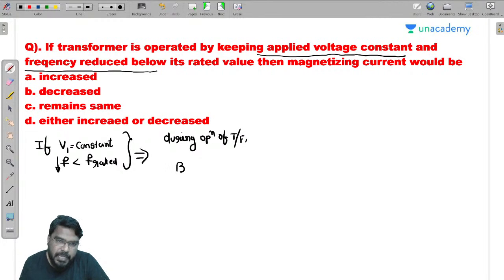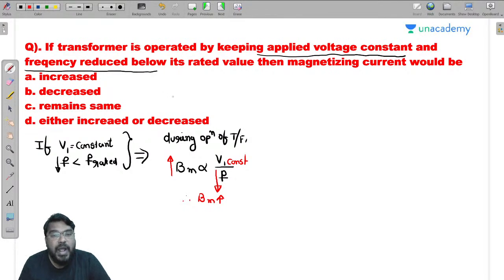the maximum flux density of the transformer is directly proportional to the V1 by F ratio. Got it? Here the applied voltage is constant and the frequency of the transformer is reduced below its rated value. So by keeping the applied voltage constant and reducing the frequency, the maximum flux density of the core will increase. Therefore B maximum will increase due to this condition. So then what will happen? B maximum is equal to phi maximum divided by the net cross-sectional area of the transformer core.